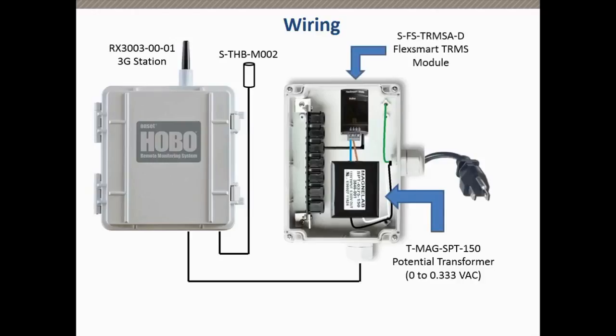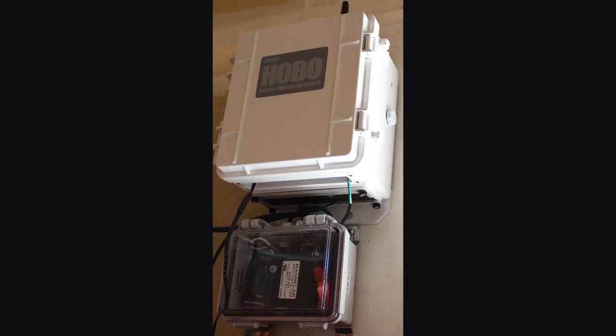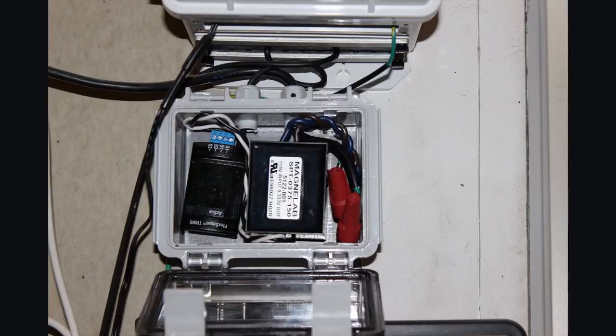We're also using the FlexSmart TRMS module, the smart module that will take the output of that potential transformer and monitor it and allow it to be monitored by that RX3000. And it's in the S-Adapt 6 external housing. In our configuration, we used a smaller housing just because of space constraints. Here's a photograph of the actual installation. You can see the RX3000 on top, the small enclosure underneath that. Here's a little zoomed in shot of that small enclosure, and now what I'd like to do is show you that HOBOlink configuration of how we set up the alarm so we can be notified if there's a problem.